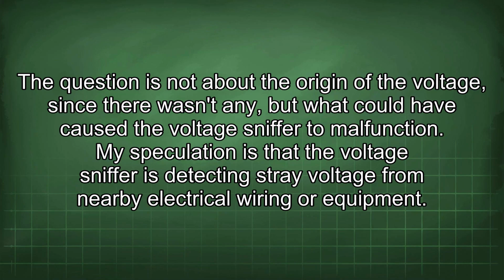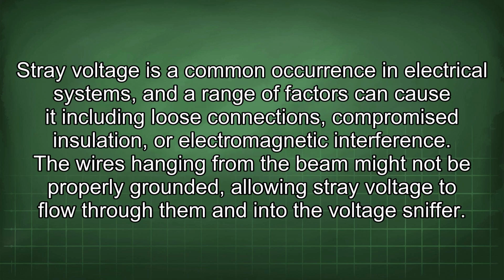The question is not about the origin of the voltage, since there wasn't any, but what could have caused the voltage sniffer to malfunction. My speculation is that the voltage sniffer is detecting stray voltage from nearby electrical wiring or equipment. Stray voltage is a common occurrence in electrical systems, and a range of factors can cause it, including loose connections, compromised insulation, or electromagnetic interference.